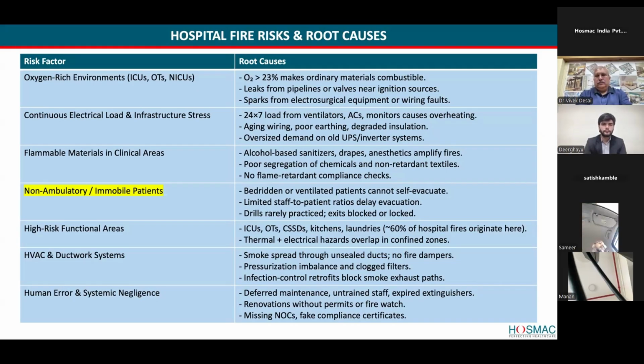So what happens when the fire gets detected? The fire alarm panel sends a signal to the AHU panel and the respective fire damper to cut off. So the starter panel of the AHU gets a signal from the fire alarm panel to switch off. So the AHU motor gets tripped, and in parallel, the fire damper which is mounted in the supply and return duct closes. Because of this isolation at both the ducts, the smoke doesn't spread into the premises. That is the key during a fire. Apart from that, here you have stopped the circulation of the smoke inside the premises, and another system is a smoke exhaust system, which is a separate system.